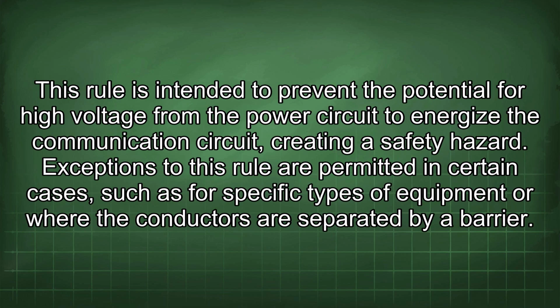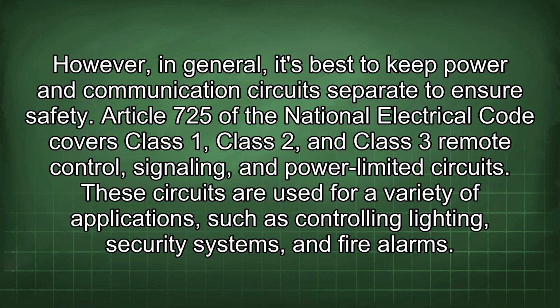This rule is intended to prevent the potential for high voltage from the power circuit to energize the communication circuit, creating a safety hazard. Exceptions to this rule are permitted in certain cases, such as for specific types of equipment or where the conductors are separated by a barrier. However, in general, it's best to keep power and communication circuits separate to ensure safety.